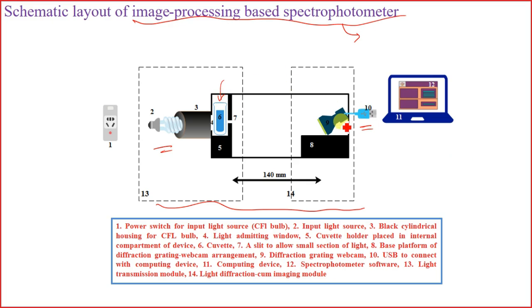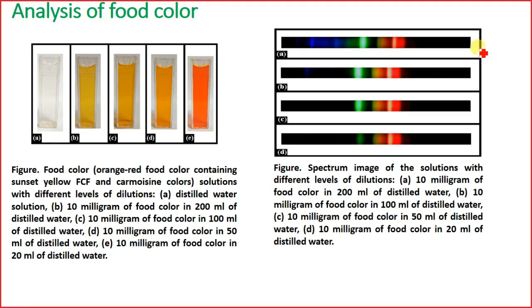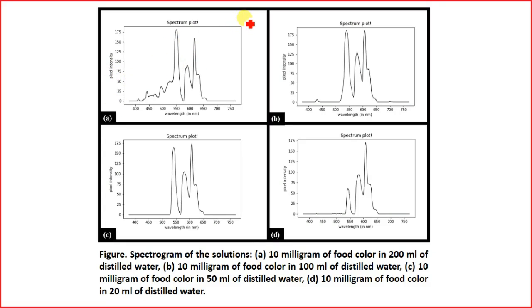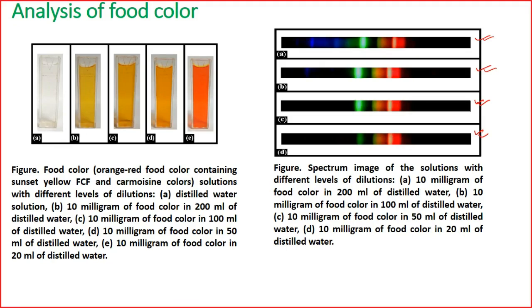Initially you measure the spectrum of the reference solvent and keep it recorded in memory. When measuring the test sample, you get its full spectrum, then subtract the reference values from the test values to obtain the corrected spectrum. If you are making your own device, you must first calibrate your sensor using a known light source, because a specific light source will give you a specific wavelength spectrum.